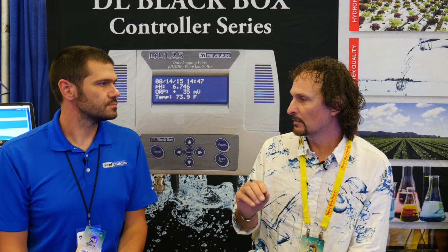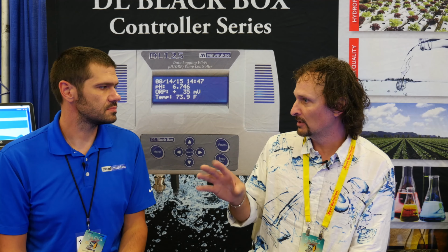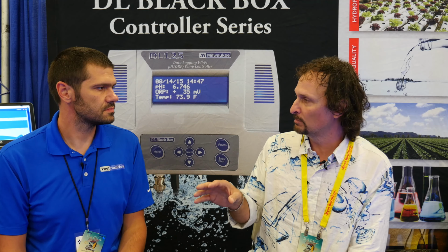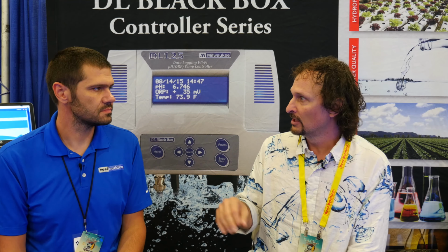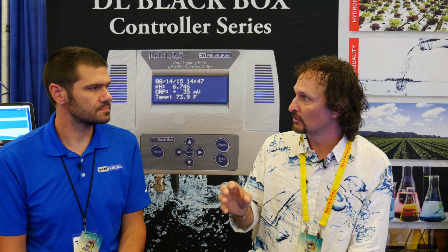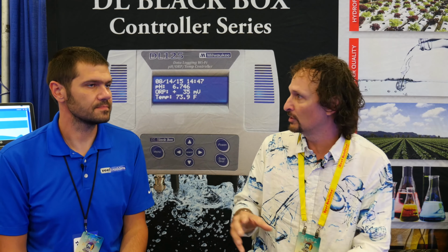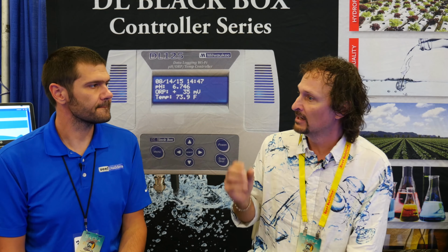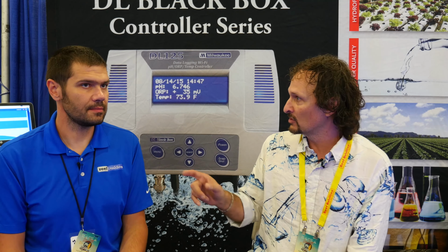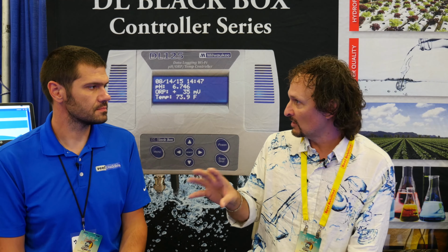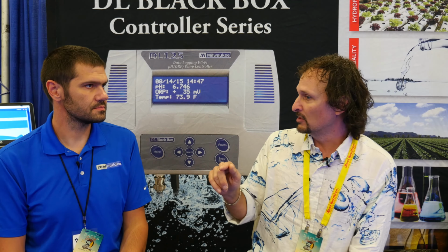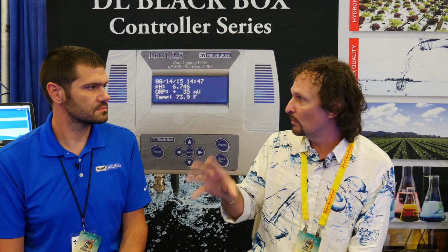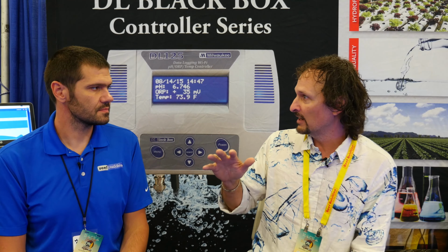So what are some of the other applications of your pH probe? Besides just measuring the pH, what else can you do with it? Well, the pH only, the DL122, which controls pH, it also has incremental dosing control. So it's separate from your pH control. So not only are you able to control your pH function, like your solenoids and things like that, it's got incremental dosing, so you can go in, select your days. It's got automatic calculations, so if you say, I want to dose 5 milliliters 10 times a day or whatever, you can do that. It does the automatic calculations for you, spreads it out over that time range.